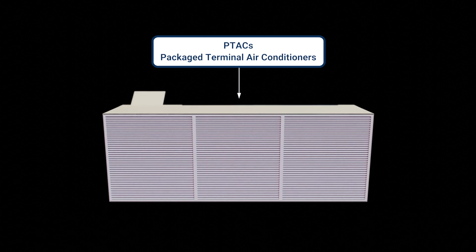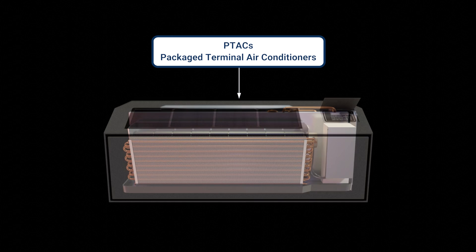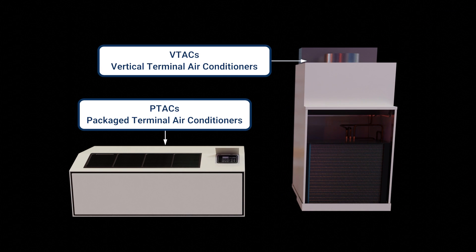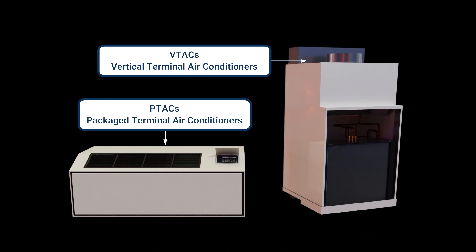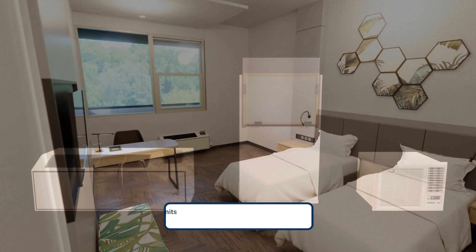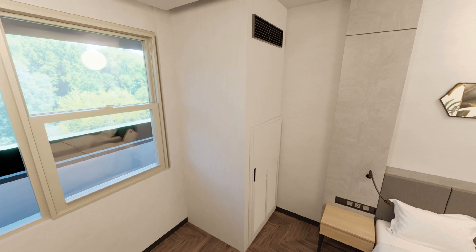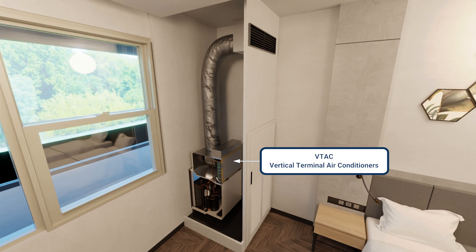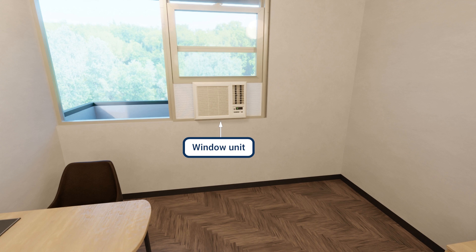PTACs, or Packaged Terminal Air Conditioners, and VTACs, Vertical Terminal Air Conditioners, as well as window units, are self-contained units often used in hotels or apartments. These are compact air conditioners, often with lower efficiency than other options. Window units are installed in windows, serving single rooms. PTACs and VTACs don't rely on the window, but they do rely on an external penetration to exchange heat to the outside.